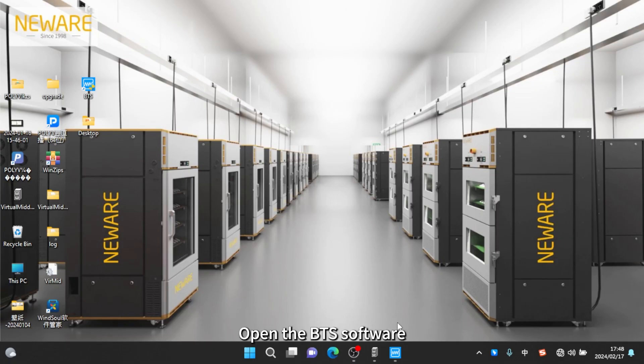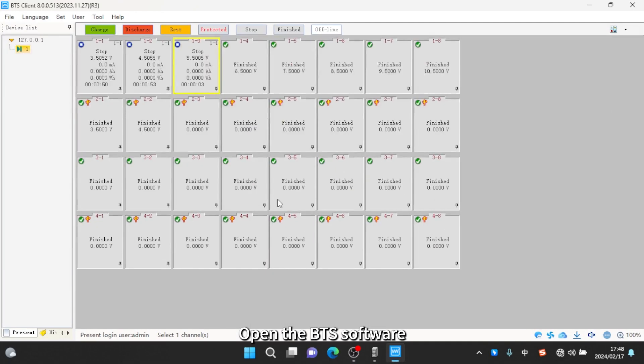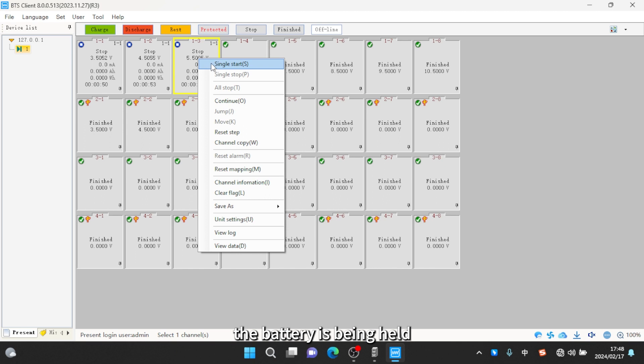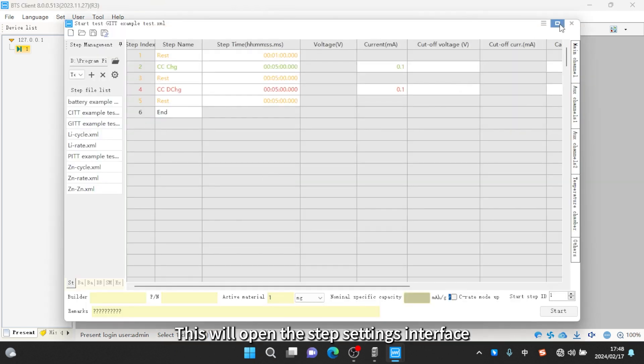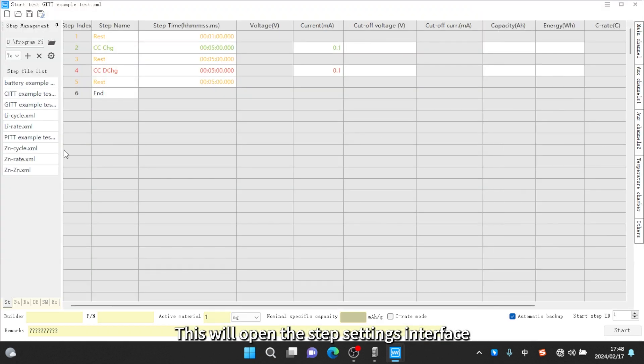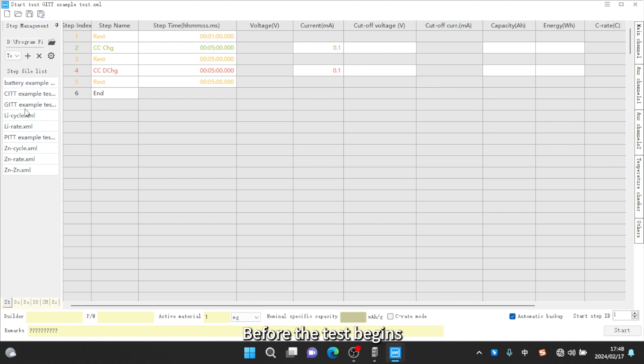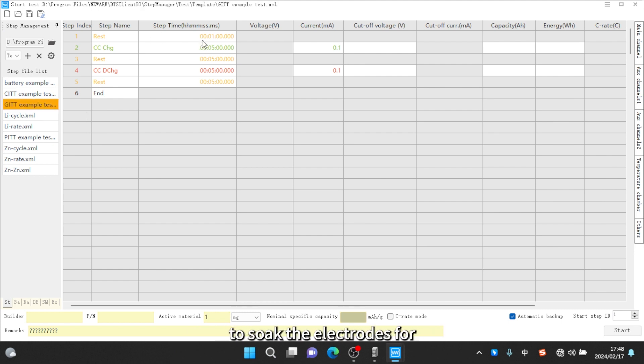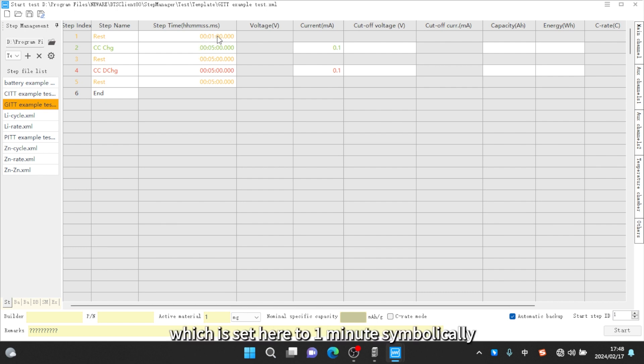Open the BTS software, right-click on the channel where the battery is being held, and click single start. This will open the step settings interface. Before the test begins, the battery needs to be left to soak the electrodes for a set period of time, which is set here to one minute symbolically.